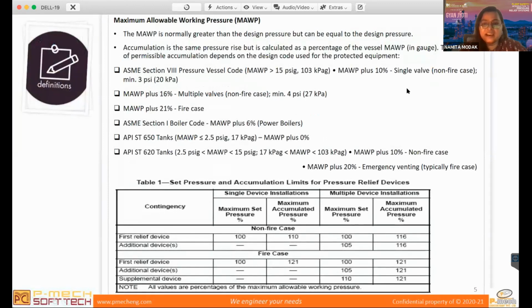Okay, so basically, as I explained already, the overpressure criteria are to be considered. If you refer to this table, this table is from API 520. So if you see the first relief devices. One more thing I would like to say: from my calculation, the required orifice size, if one orifice is not sufficient, let's say the maximum size given in API 526 is the T orifice. If I use the T orifice but still there is an additional area required for my scenario, then I have to use 2 orifices. That may be lesser than T, maybe 2 R type orifices or any other F type of orifice.